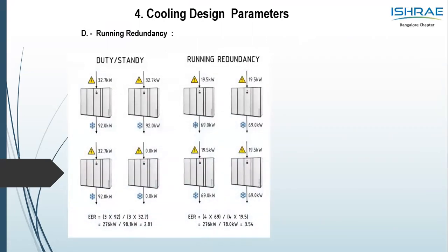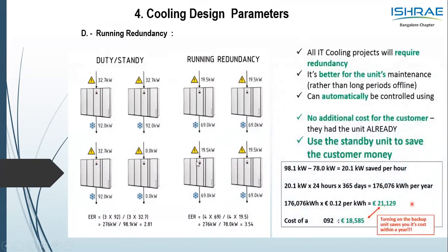We talked about tier 1, tier 2, and tier 3, where we spoke on N plus 1, 2, N plus 1. So not just for tier design or R design, but also quoting you an example of saving, considering running a redundancy, let's see a case study of 4 units where each of these capacities is 92 kilowatt of cooling capacity. This is as a standby, 3 are working. So when you calculate 3 into 92, the total capacity is 276. Vis-a-vis the power consumption by each of these units running at 100% is 32.7. Just a case study and a sample example. Into 3 gives you a COP of 2.81.